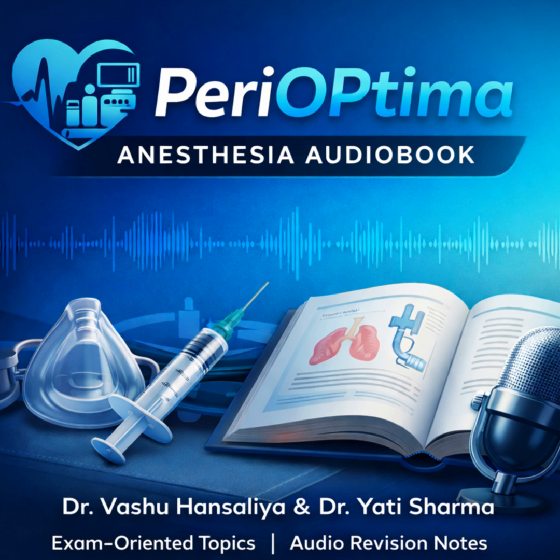The parameters are usually around 132 degrees for 3 minutes, but you must state that this is for immediate use only. Like when a surgeon drops a crucial instrument mid-case. Exactly that scenario. The instrument is sterilized, unwrapped, and must be carried directly to the sterile field. It is absolutely discouraged for routine use on full instrument sets because there is no packaging. There's no barrier to recontamination the second it leaves the autoclave.